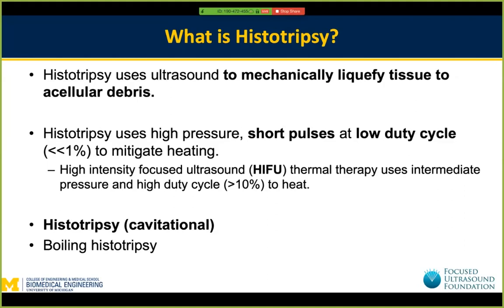Histotripsy uses high-pressure, short pulses at a low duty cycle — below 1%. That's the key distinction between histotripsy and HIFU. Duty cycle is the ultrasound on-time divided by the total treatment time. Using a low duty cycle below 1% allows us to reduce and minimize heating. In contrast, HIFU thermal therapy uses continuous wave or high-duty-cycle ultrasound trains to purposely heat the tissue.